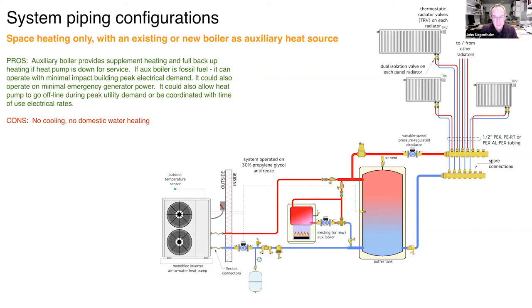When it's 20°F below zero and a four-ton heat pump is operating like one and a half tons, the balance can come from the existing boiler. This works in new construction too, but many current cases involve an existing fossil fuel boiler where clients want to add a heat pump. If the boiler is 40 years old with puddles of water around it, it's at end of life — but if it has 5 to 10 years left, it makes sense to build the system around it. Controls are available to manage operating the heat pump as the priority heat source and bringing the boiler on as needed.